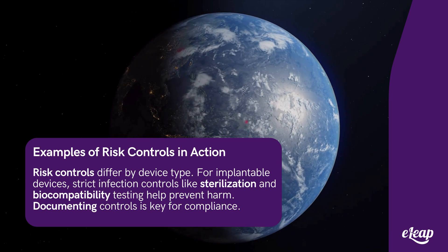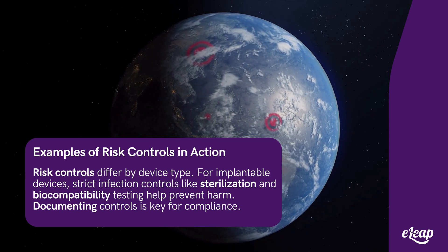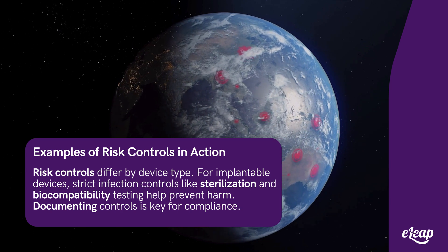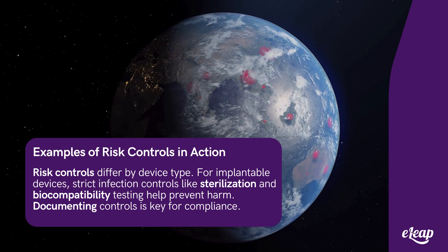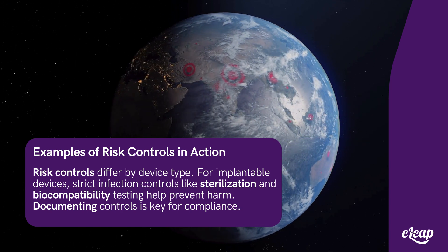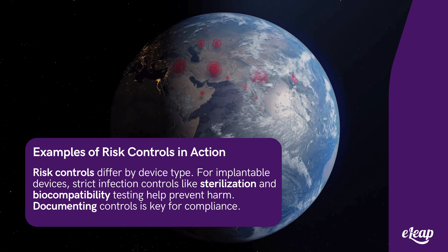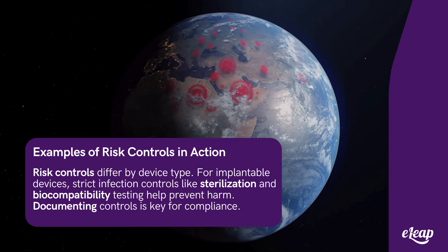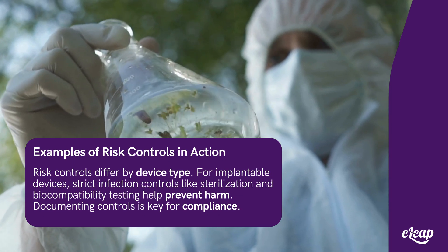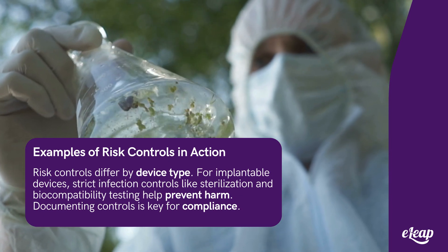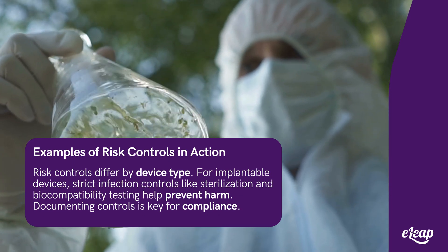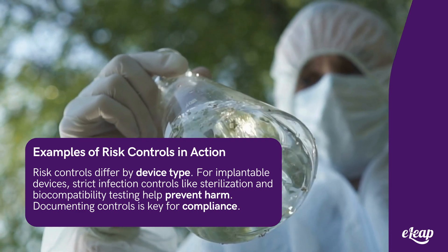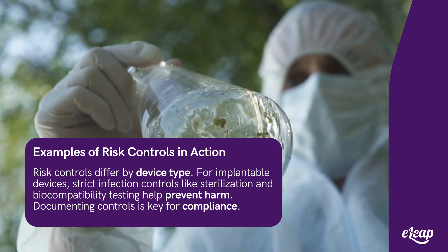Risk controls can vary widely depending on the type of medical device. For example, an implantable device manufacturer may implement strict infection control measures during production, such as using sterilized materials and performing rigorous biocompatibility testing. These controls help mitigate the risk of post-surgical infections, which could otherwise lead to serious patient harm. Documenting the effectiveness of these controls is essential for ISO 14971 compliance.